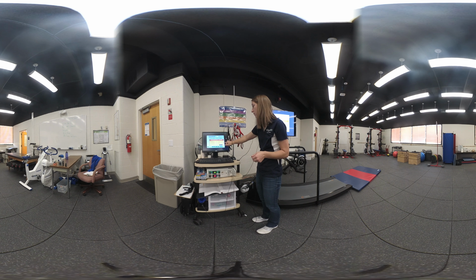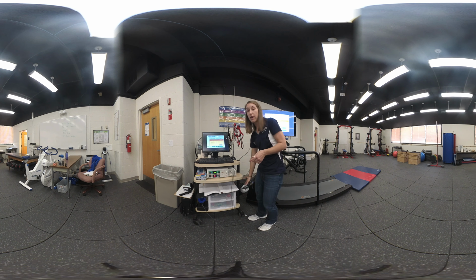and I'm going to show voltages. When I show the voltages, I want to see that I didn't get any warning signs from a previous calibration to tell me something that was very off from a previous calibration. So either that could have been the previous calibration was really incorrect, or this calibration is incorrect. And you're going to know based on using your tank what's going on. If you were to get something that's really off, you need to, one, check your gas, check your steps. You might want to recalibrate it to make sure you didn't forget a particular step.